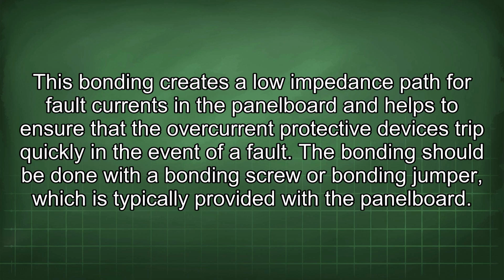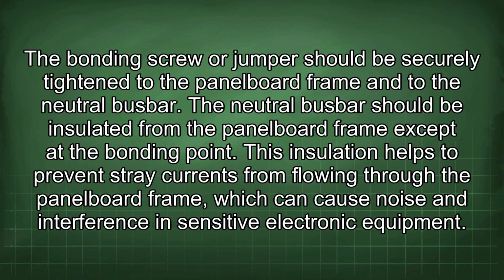This bonding creates a low impedance path for fault currents in the panel board and helps to ensure that the overcurrent protective device is tripped quickly in the event of a fault. The bonding should be done with a bonding screw or bonding jumper, which is typically provided with the panel board. The bonding screw or jumper should be securely tightened to the panel board frame and to the neutral busbar. The neutral busbar should be insulated from the panel board frame except at the bonding point. This insulation helps to prevent stray currents from flowing through the panel board frame, which can cause noise and interference in sensitive electronic equipment.